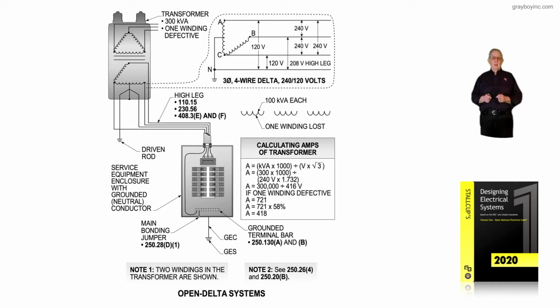In my career, I have found that open delta systems do not work as well if you have a lot of motor load. We should go to closed delta systems in that case. But now notice again, we are reviewing how we obtain our 120 volts. Are there 2 legs that we would get 120 volts on, or is there 3?